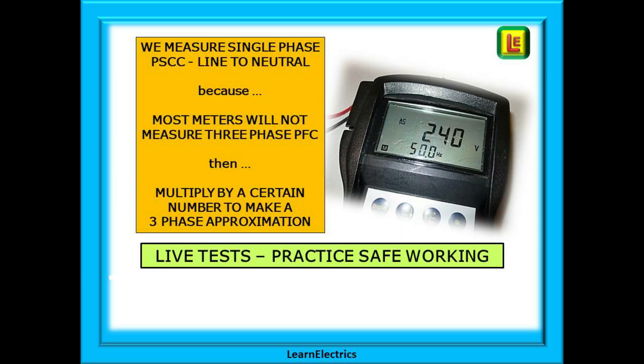Why do we measure single phase first? A line to neutral measurement of the prospective short circuit current, or PSCC, is made because most multi-function testers will not measure three-phase fault currents. So we measure at 230 volts and then multiply by certain numbers to arrive at the 400 volt three-phase answer. Remember that these are live tests and suitable precautions must be taken and safe working practiced.